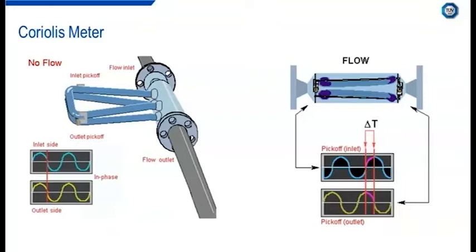Coriolis meters are now also being used for density measurement as opposed to mass measurement, and are actually, in some applications, the preferred choice over densitometers. They can be used to monitor contamination in oil and water mixtures, for example, and this is something that we are also carrying out here at the National Engineering Lab, using Coriolis meters for their density output as well as direct mass measurement.